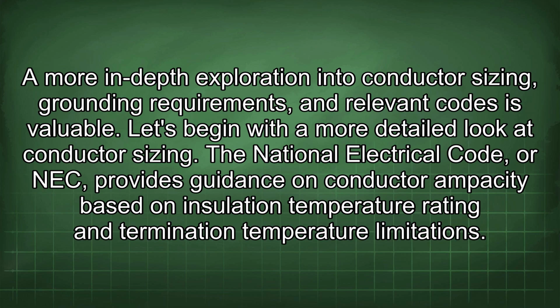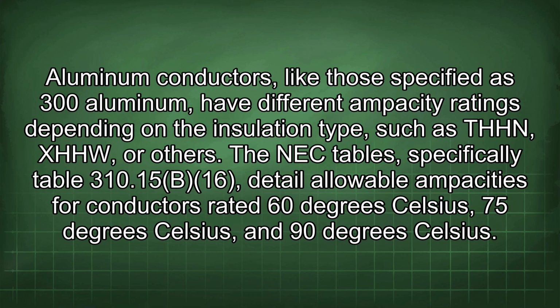A more in-depth exploration into conductor sizing, grounding requirements, and relevant codes is valuable. Let's begin with a more detailed look at conductor sizing. The National Electrical Code, or NEC, provides guidance on conductor ampacity based on insulation temperature rating and termination temperature limitations. Aluminum conductors, like those specified as 300 aluminum, have different ampacity ratings depending on the insulation type, such as THHN, XHHW, or others. The NEC tables, specifically Table 310.15(B)(16), detail allowable ampacities for conductors rated 60 degrees Celsius, 75 degrees Celsius, and 90 degrees Celsius.